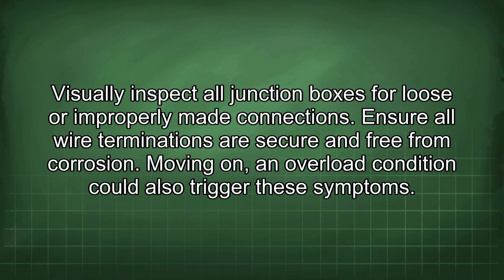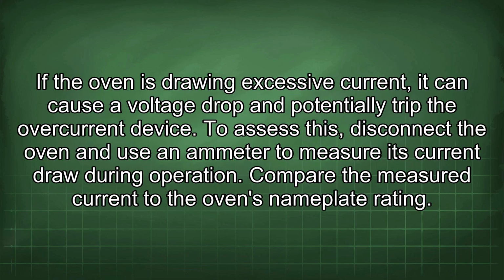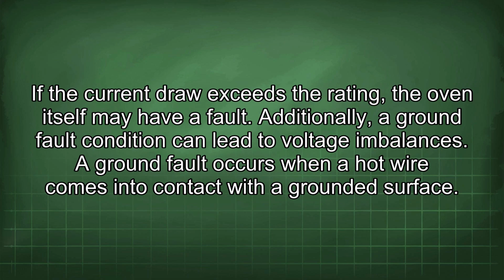Moving on, an overload condition could also trigger these symptoms. If the oven is drawing excessive current, it can cause a voltage drop and potentially trip the overcurrent device. To assess this, disconnect the oven and use an ammeter to measure its current draw during operation. Compare the measured current to the oven's nameplate rating. If the current draw exceeds the rating, the oven itself may have a fault.